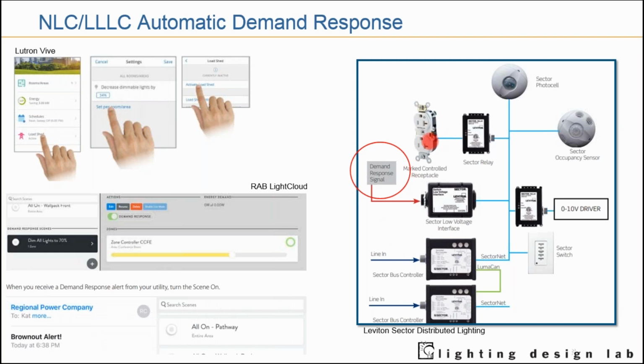Same deal with a more digital response. This is the Lutron Vive dashboard. You can pre-program that whenever a demand response or load shed signal is received, be it analog, Ethernet, or BACnet, all lights decrease by 34%, and it'll automatically do that. That's the easy way, all lights decreasing by an amount, but you can also go space by space to reduce the lights of a specific room to a specific level.